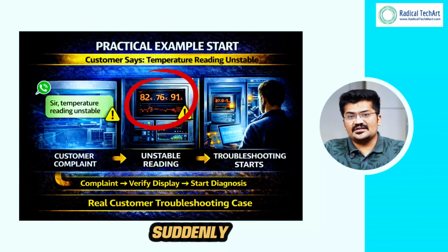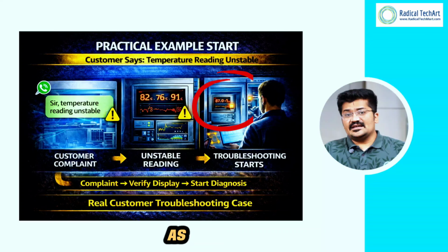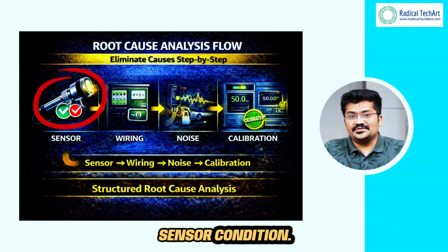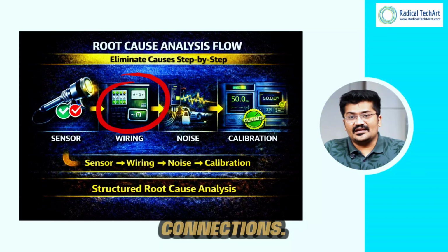Let us consider a practical scenario. A customer reports that the temperature reading in their process suddenly becomes unstable. As an engineer, you begin troubleshooting. First, you check the sensor condition. Then you inspect the wiring connections.